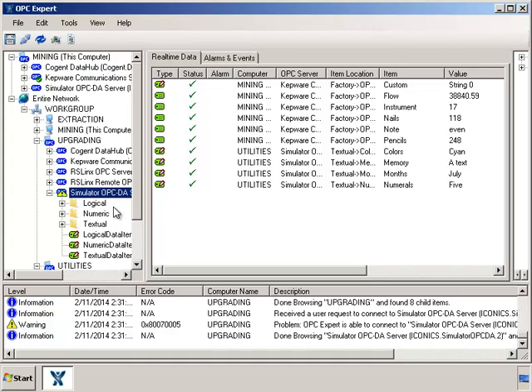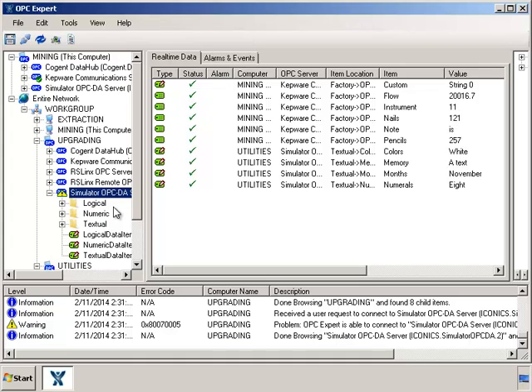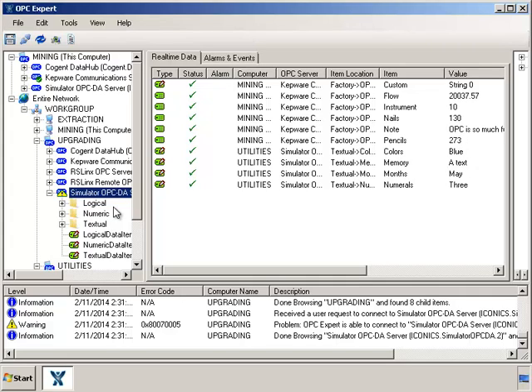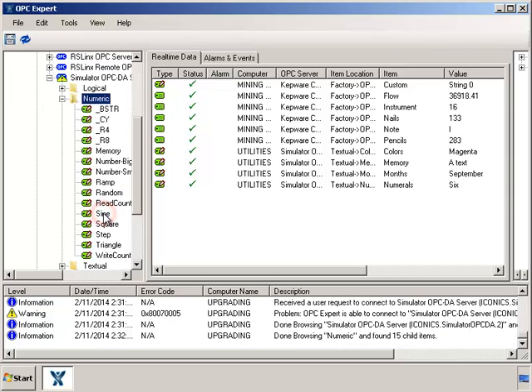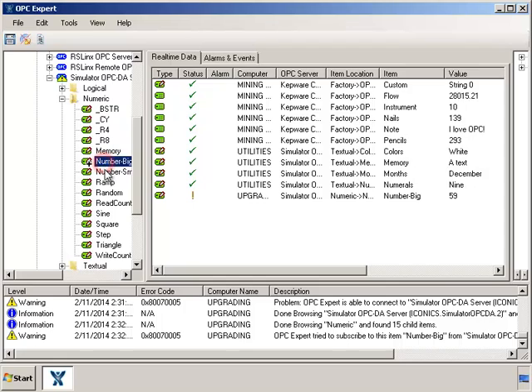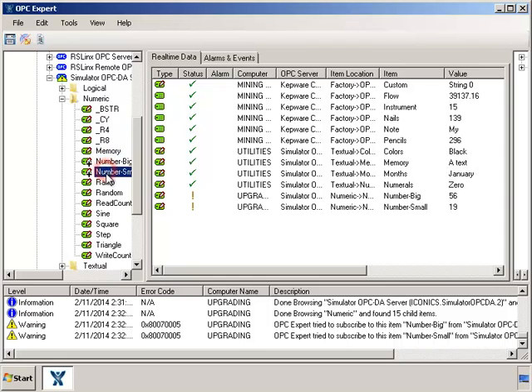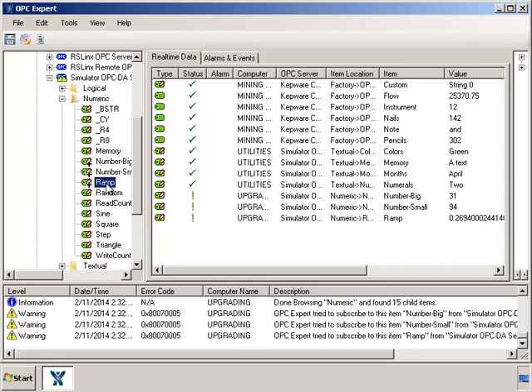You see, even though OPC Expert detected a problem, it still enables me to see data in my OPC servers. Let's drill in and subscribe to some items. The exclamation mark indicates I have a problem with these items. When I look at the message window, I can see OPC Expert tells me there is a problem.